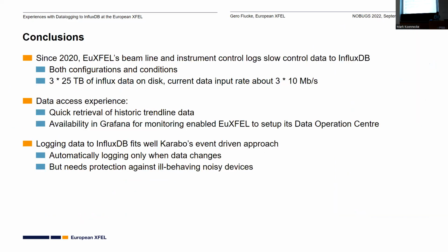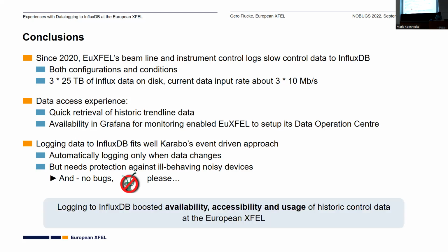To conclude, since 2020, European XFEL has streamlined instrument control logs, slow control data, to InfluxDB, both configurations and conditions. We have 25 terabytes on disk. We have experienced really nice, quick retrieval of data, and really flexible queries are possible. This allowed our data operations center to monitor constantly. Data logging to InfluxDB fits well to Karabo, but we need protection against noisy, misbehaving devices. And, well, no bugs, please. Finally, logging to InfluxDB boosted the availability, accessibility, and usage of historic control data at European XFEL. Thank you.